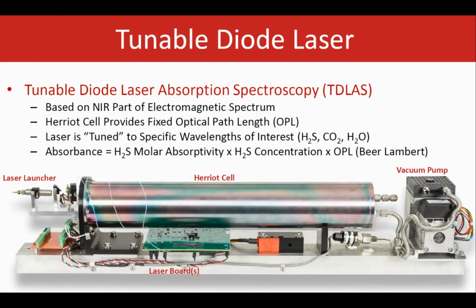In our case, for example, the length of the Herriott cell is 52.6 centimeters, and light goes back and forth 100 times, so an overall path length of 52.6 meters can be achieved. At the end, the light exits the cell and gets detected by the detector, and finally, the concentration can be calculated from the detector's output on how much light is absorbed, using the Beer-Lambert law. So that's how that works.